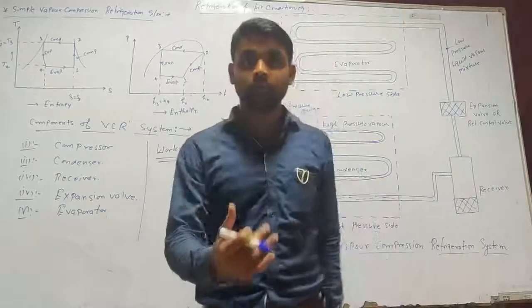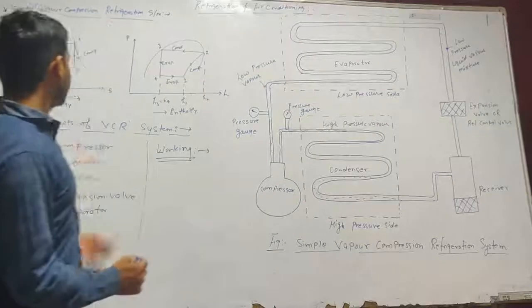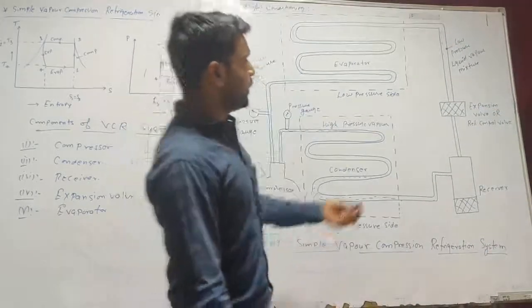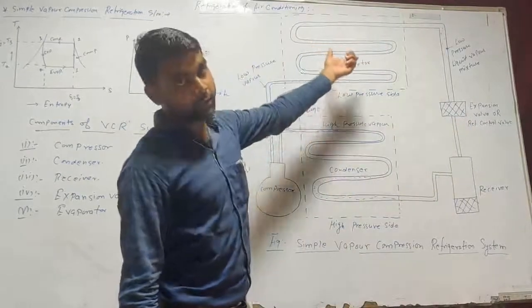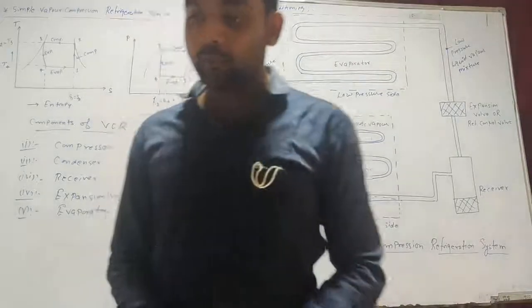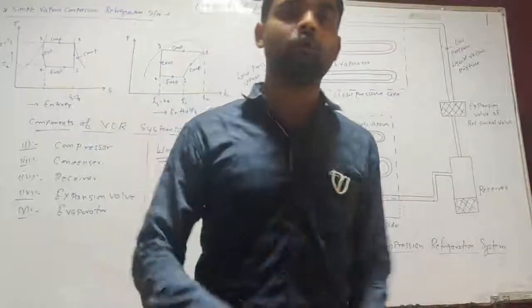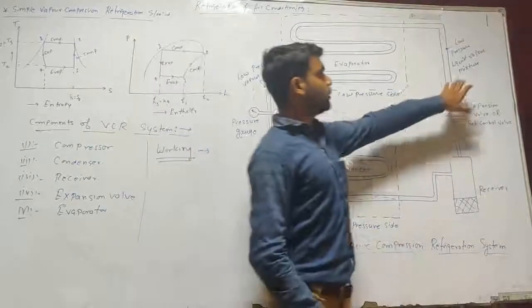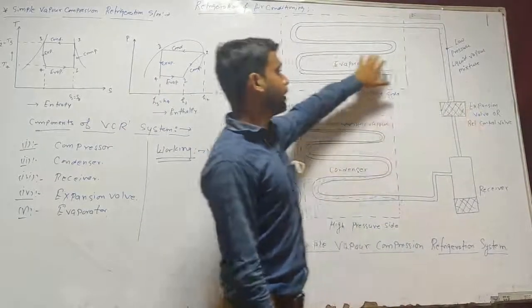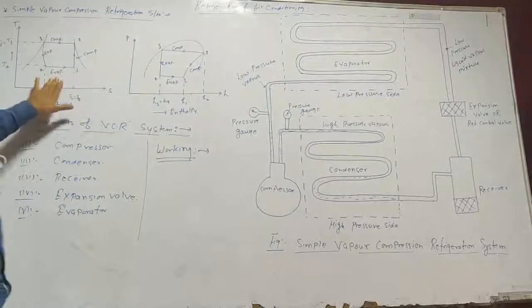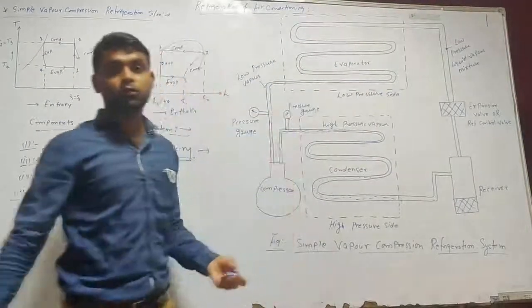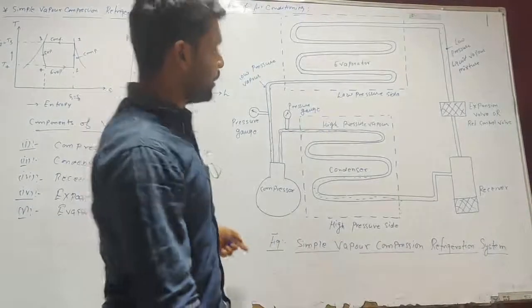During expansion, the temperature and pressure decrease, and the liquid refrigerant changes into a low pressure liquid-vapor mixture. From the expansion valve, the refrigerant comes to the evaporator. The evaporator absorbs the latent heat of vaporization from the medium. At constant pressure and constant temperature, the refrigerant changes to vapor and then circulates back to the compressor. This is how the cycle continues.